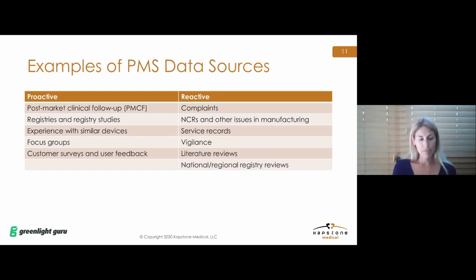So as mentioned previously, many companies have performed some post-market surveillance activities. However, these have been very reactive, or in other words, not specifically planned for. Some common reactive approaches include complaint handling, non-conforming reports and other issues in manufacturing, service records if applicable to your device type, vigilance, literature reviews, and then looking at national regional registry reviews. So it's really just taking existing data and analyzing it. But what the new MDR is looking for is that the manufacturer is proactively collecting data on the device before a deficiency has occurred. So some proactive approaches are post-market clinical follow-up, again, registries and registry studies performed by the manufacturer, experience with similar devices, focus groups and customer surveys and user feedback. So here I'm introducing the term post-market clinical follow-up for the first time.